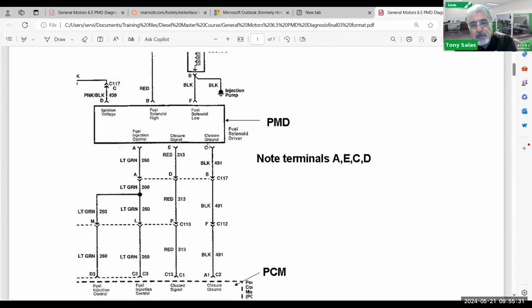Now you're probably asking, where do we see this? Well, that pink and black wire on terminal D - what we found is that on earlier model 6.5s, it's going through a fusible link. A fusible link is a few gauges smaller than the actual wiring, and they do that intentionally so that in the event it gets hot from high current draw, it burns. What we recommend is putting a relay in the circuit - I can get you diagrams on that if needed - because that ensures we're getting full battery voltage going to terminal D.